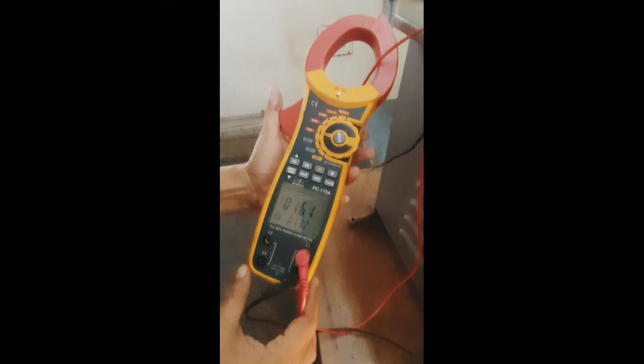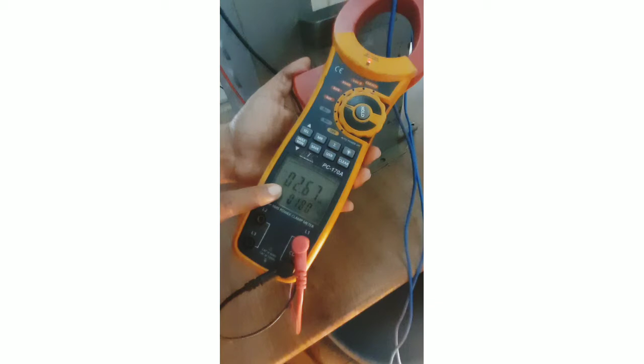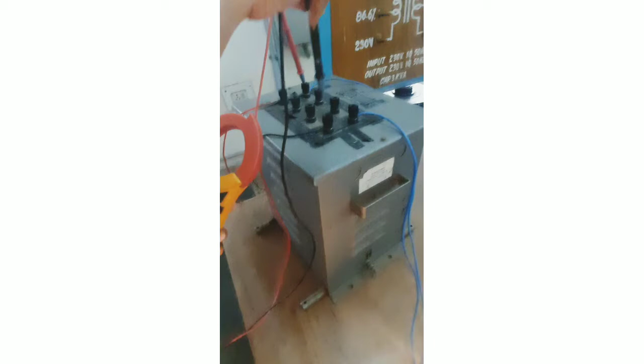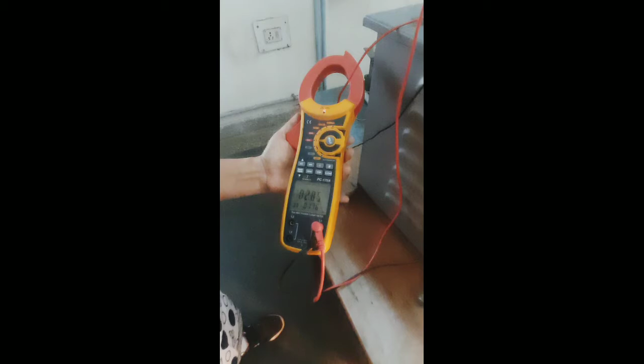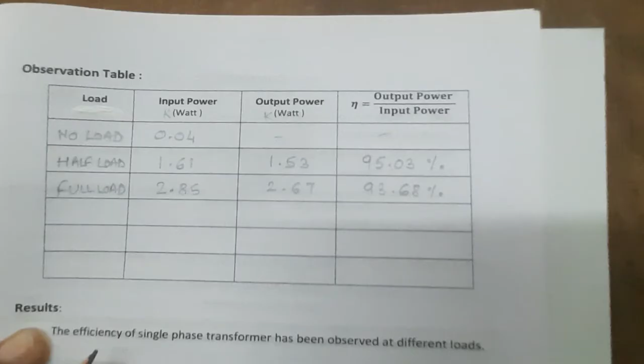Next we will see the reading at full load. In the last case we completely connect the load to the secondary side, the full load case. You can see the lamps are switched on, and now we see the wattage reading at the secondary. It is 2.67 kilowatts at the secondary side, and the reading at the primary side is 2.85 kilowatts.